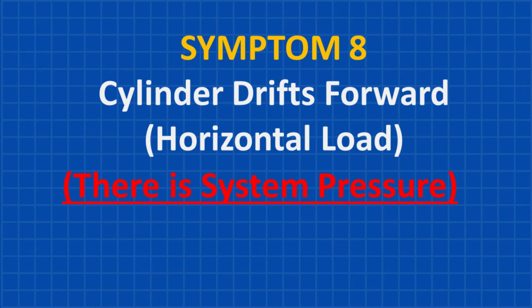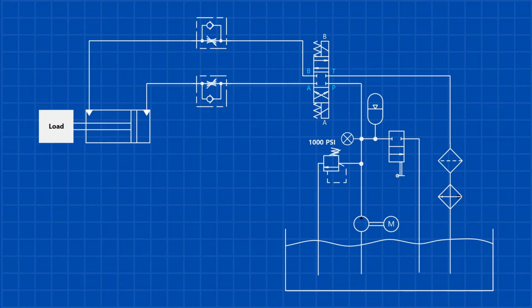Symptom 8. Cylinder drifts forward, horizontal load. There are two main reasons this could be happening. First, if the center block valve is leaking internally, it can let oil flow into both the blind end and the rod end of the cylinder. Since the blind end has a larger surface area than the rod end, this creates a force imbalance, causing the cylinder to drift forward. The second common cause of cylinder drift is internal leakage past the piston seals.